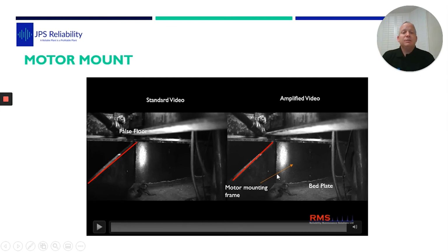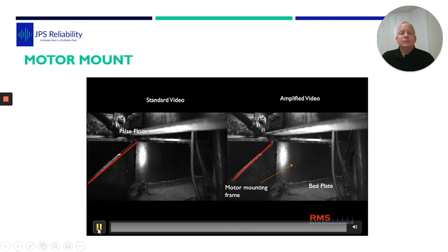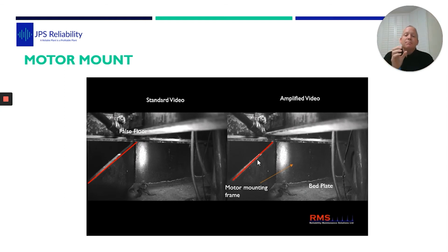Can you put the camera underneath? So this is the webbing or the gusset. That's the big round flange, motor, and your bed plate. You can see there that bed plate is just twisting. And what was great was that the frequency of motion, what we got off MA, was bang on to the VA. Now, once we had this, we showed the client this. So this is 2017, this is like new technology. They accepted that the motor repairer was fine and that the issue was structural on site, coincidentally with when they changed the speeds. That was great.